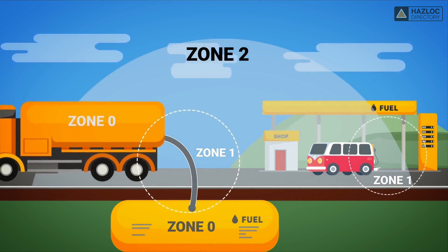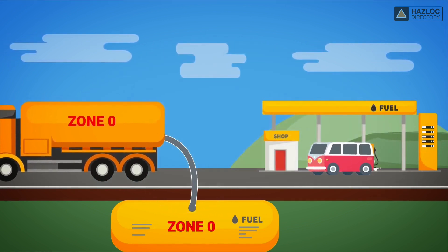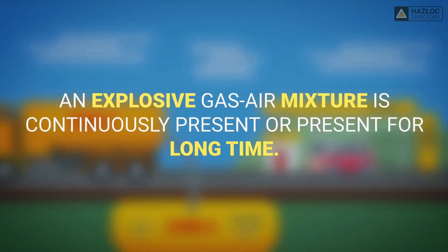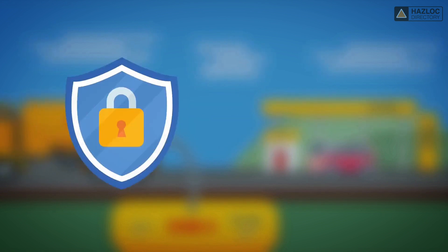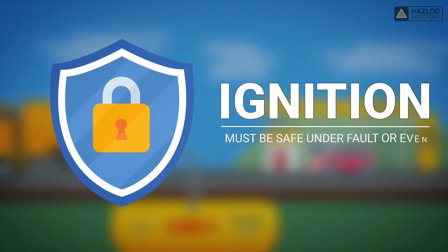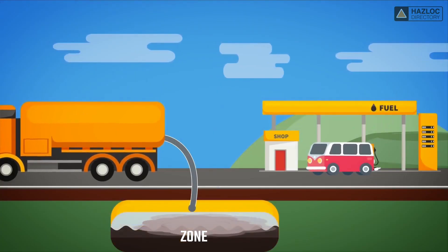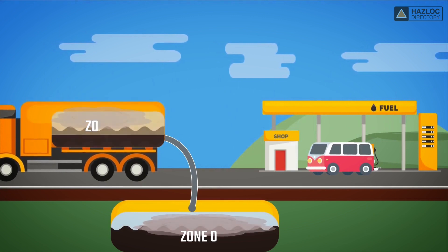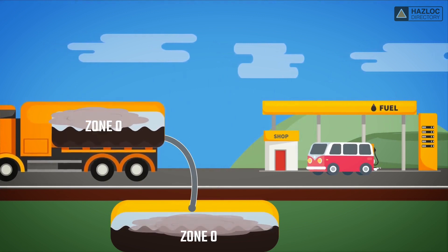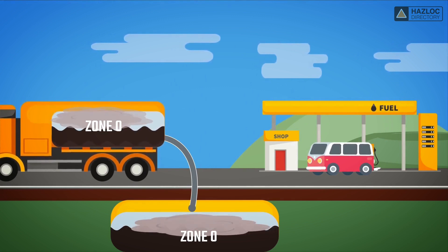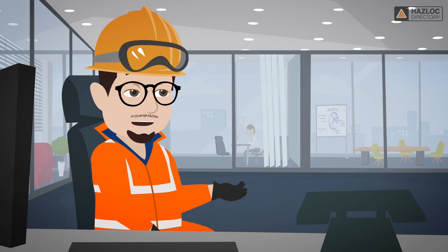In this animation, our focus is on the Zone 0 classified area. Zone 0 is an area where an explosive gas-air mixture is continuously present or present for a long time. Therefore, devices that can pose an ignition risk must be safe under electrical fault as well as normal conditions. In this illustration, we have a storage tank that contains flammable liquid. Above the flammable liquid inside the tank, and given an ambient temperature above the flashpoint of the liquid, gas vapors can be present. This area is considered Zone 0 because the hazard exists continuously, and the product being used in this area must be safe.